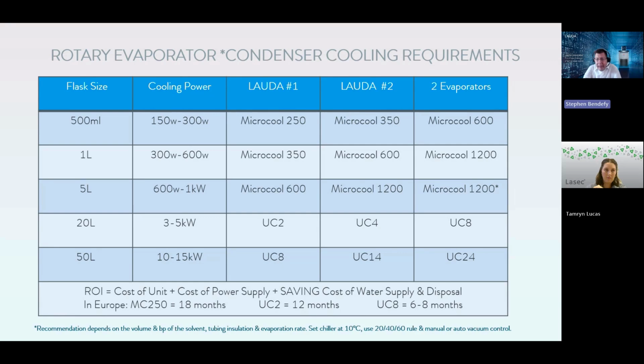If there are bigger applications, we mentioned before about the spectrophotometers, the larger scale rotary evaporators, 50 litre, 100 litre, or maybe a more kilo lab or even plant size cooling, where we require 10, 20. At LAUDA, we offer cooling systems going up to 250 kilowatt cooling supply.